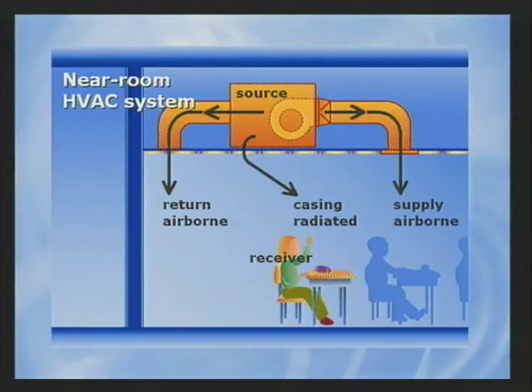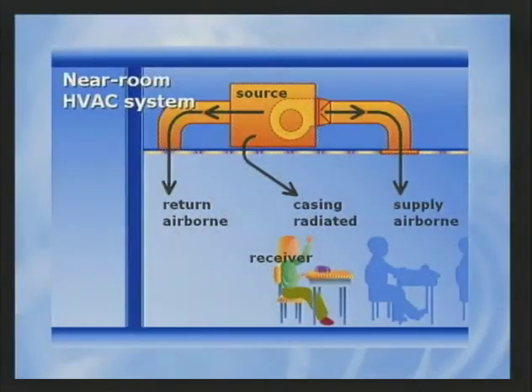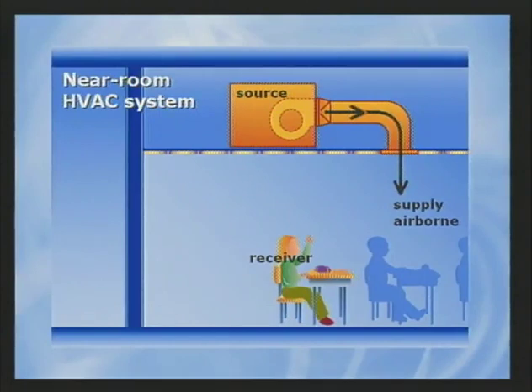In most cases, it's also wise to check the duct breakout sound from the supply and return ducts. To make the model as accurate as possible, start with unit sound data that is broken into discharge, inlet, and casing components. Starting with total sound and making assumptions about how the sound is divided will reduce the accuracy of the prediction. The supply path starts with discharge sound data and follows the ductwork from the unit into the room. Ducted returns are treated in the same manner, even though the sound is traveling in the opposite direction of the airflow. If the return path is unducted, it can be lumped in with a casing radiated path. When the unit is installed above an occupied space, only the ceiling tile isolates the casing radiated sound from the receiver.